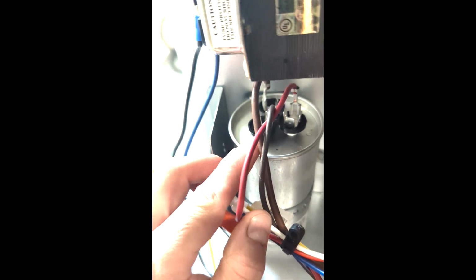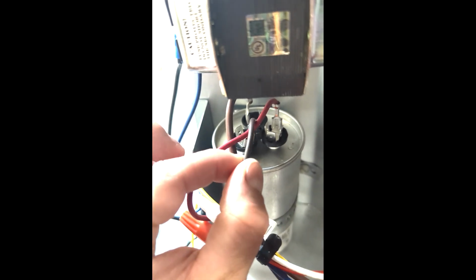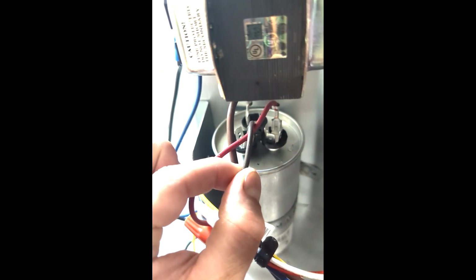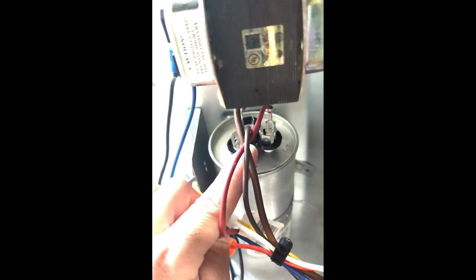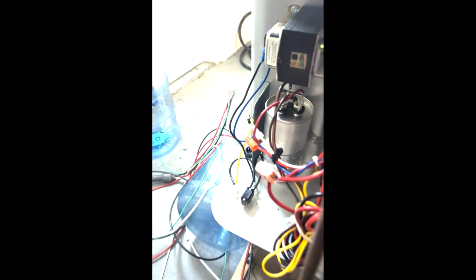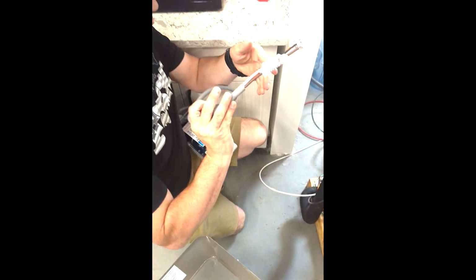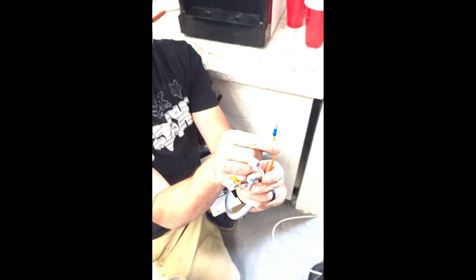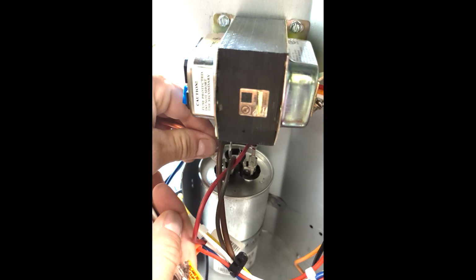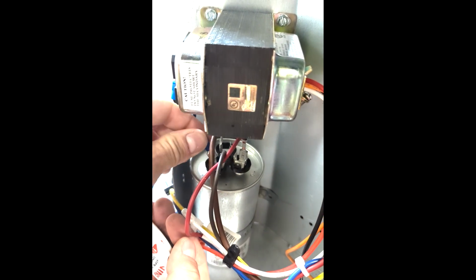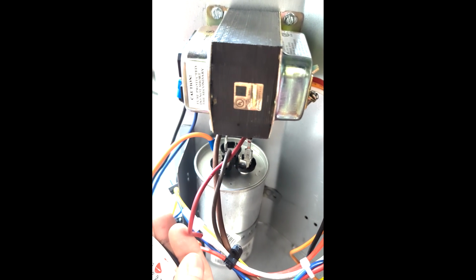So we know that this brown wire right here is the S wire from the compressor that lands on the HERM terminal, okay? So what you're going to do is take your orange EasyStart wire. You have four wires that come off your EasyStart: your orange, your white, brown, and black. We're going to take the orange one, and plug it right on the HERM terminal next to the brown wire, okay?